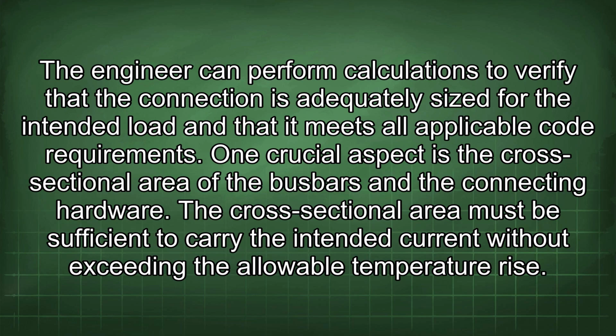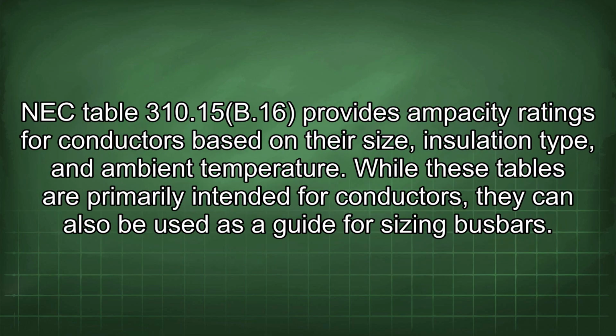One crucial aspect is the cross-sectional area of the busbars and the connecting hardware. The cross-sectional area must be sufficient to carry the intended current without exceeding the allowable temperature rise. NEC Table 310.15(B)(16) provides ampacity ratings for conductors based on their size, insulation type, and ambient temperature. While these tables are primarily intended for conductors, they can also be used as a guide for sizing busbars.